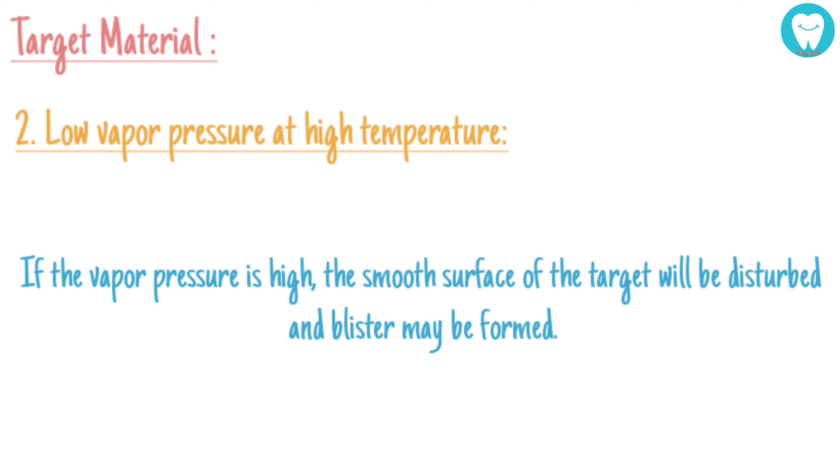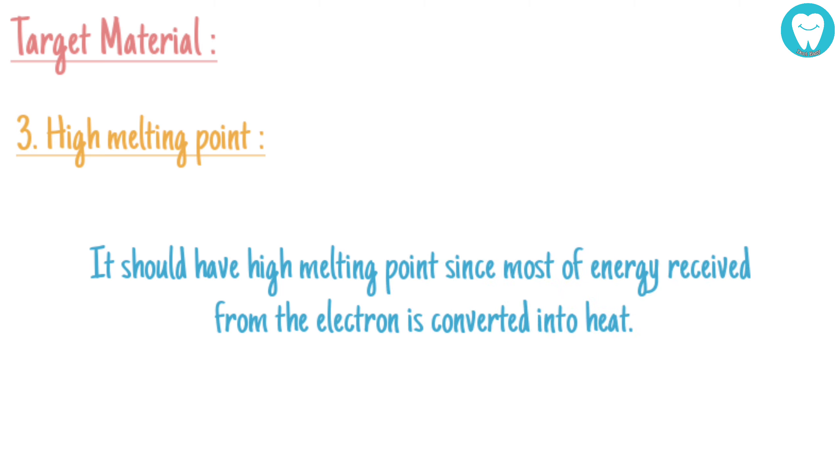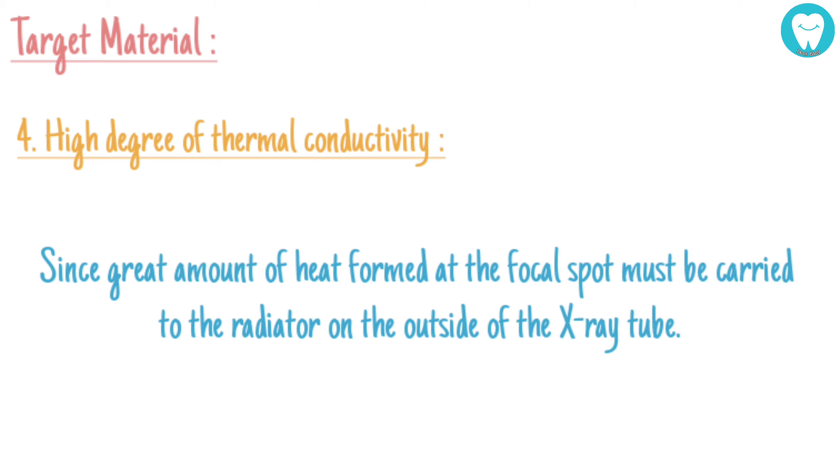Third, high melting point. It should have a high melting point since most of the energy received from the electrons is converted into heat. High degree of thermal conductivity. Since great amounts of heat formed at the focal spot must be carried to the radiator on the outside of the X-ray tube.